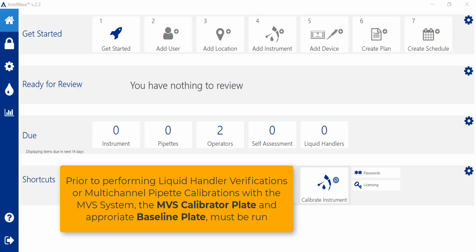Before you begin any automated liquid handler verifications or multi-channel pipette calibrations using the MVS system, you'll be required to run the MVS Calibrator plate as well as a baseline plate, either 96 wells or 384 wells if that's applicable, before you perform those tasks.